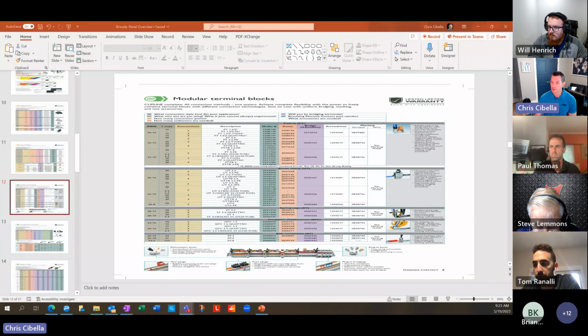Okay. Next one here is insulation displacement. This is where you take a wire coming off the reel, you blunt cut it, stick it in the terminal block, and then this orange part is a movable piece. Typically, orange in our world is movable. You rock it forward, and it will pierce the outside sheathing of the wire jacket and make a gas-tight connection. Not very popular.